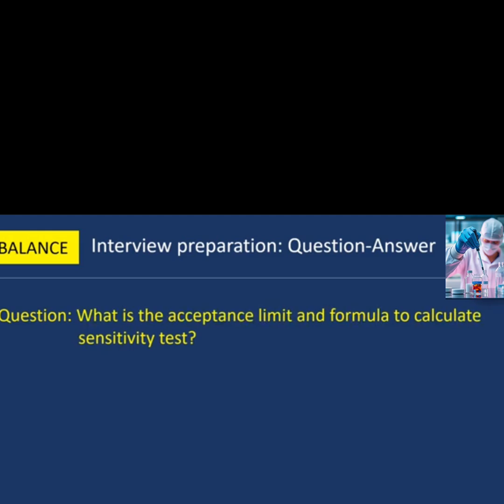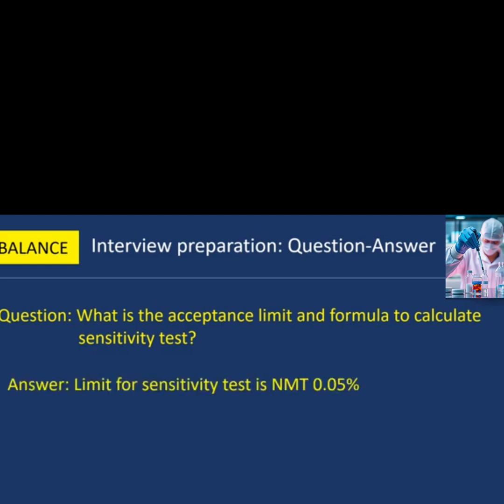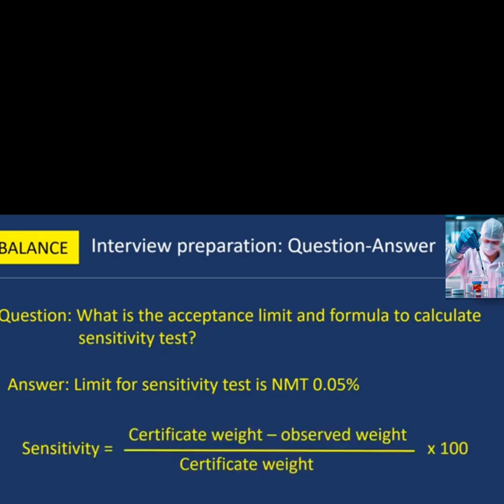Next question: what is the acceptance limit and formula to calculate the sensitivity test? The limit for the sensitivity test is not more than 0.05%. The formula is: Sensitivity = (Certificate Weight − Observed Weight) ÷ Certificate Weight × 100.